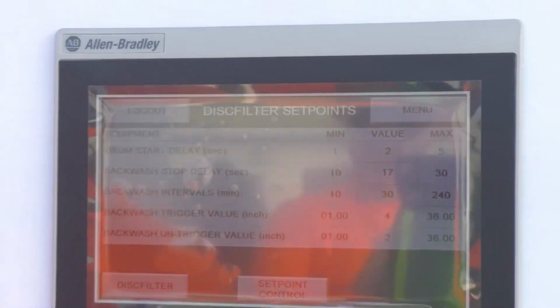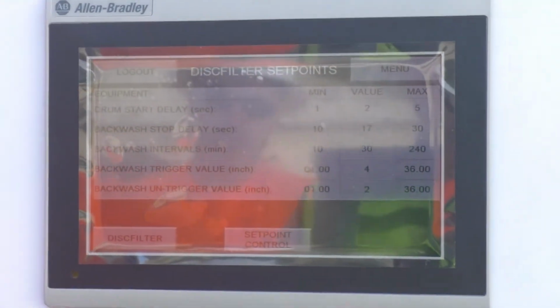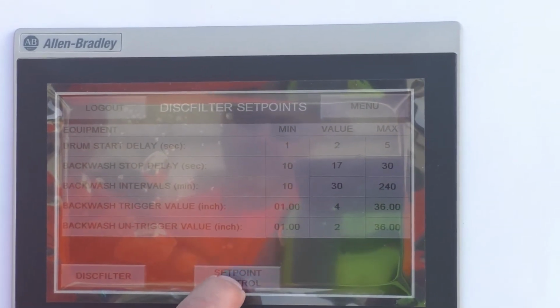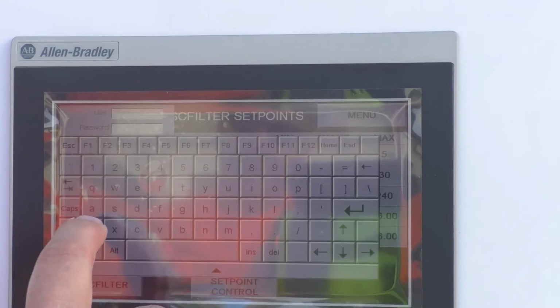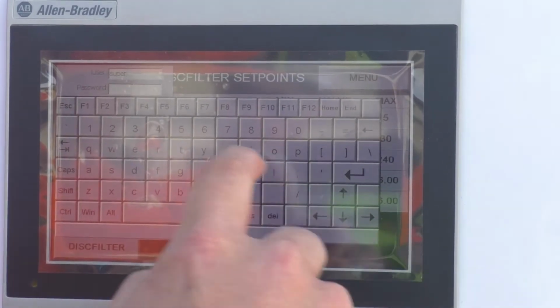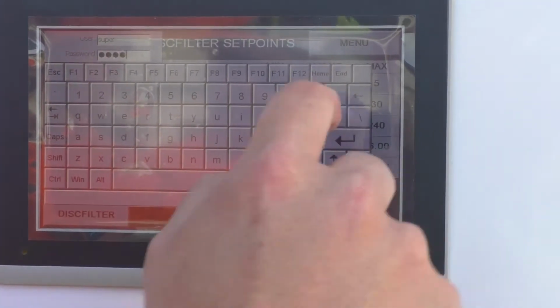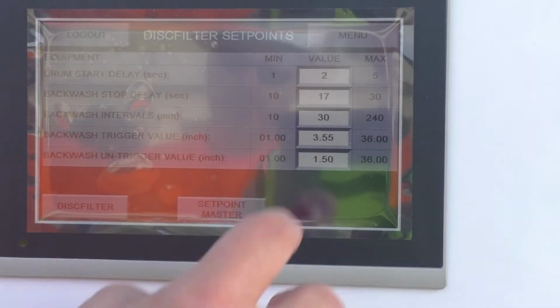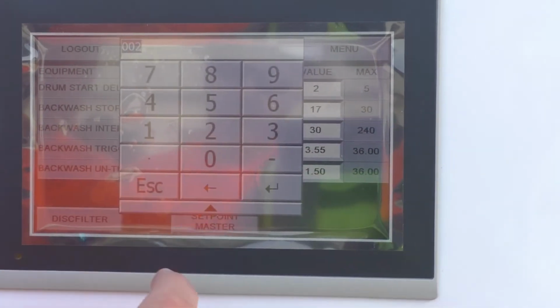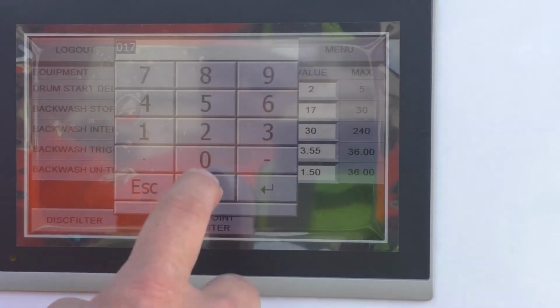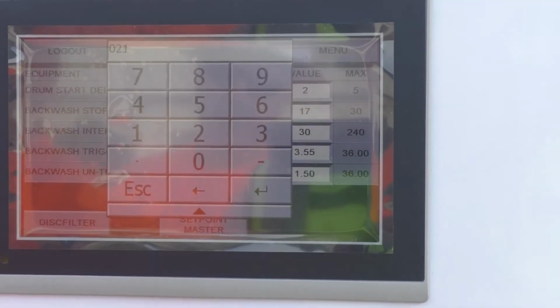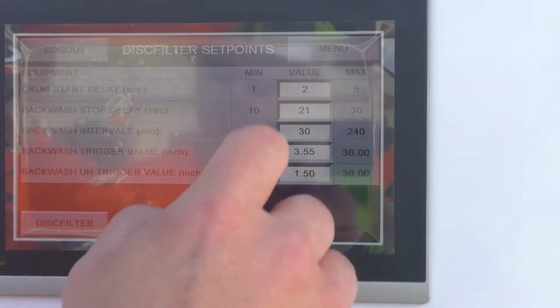If you need to change any of this, if you realize you're starting to have a lot of solids, something changes, and you want to up the backwash time to 21 seconds, you hit control, same thing as back there, super. Now you should be able to change whatever you need to change. If you want to change the backwash to 21, type in 21, hit enter, and it turns to 21.